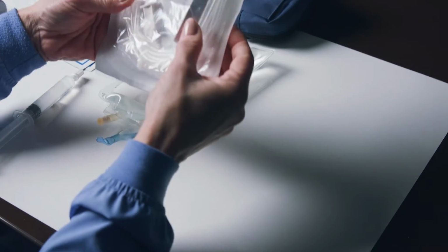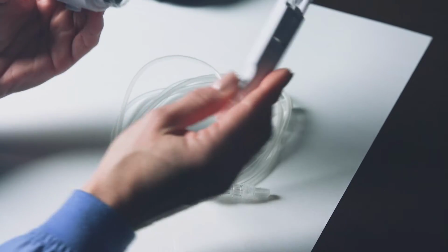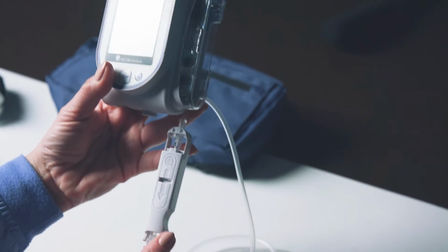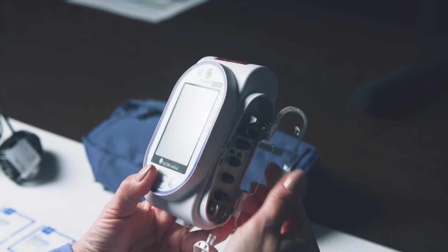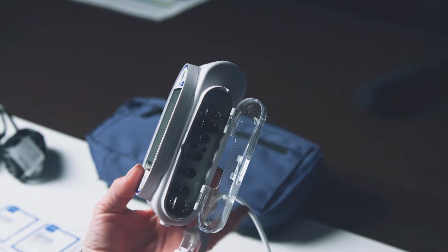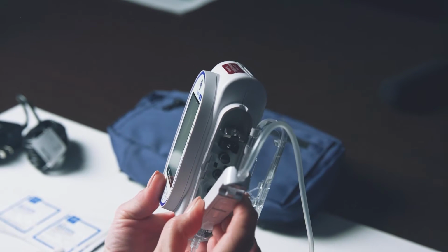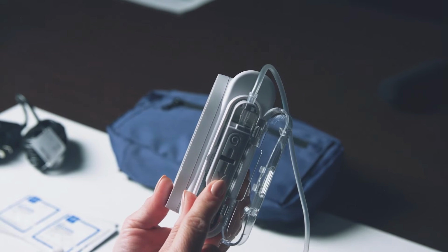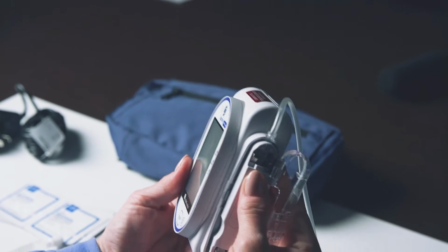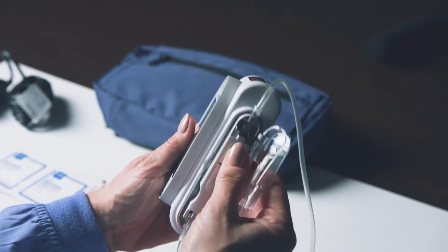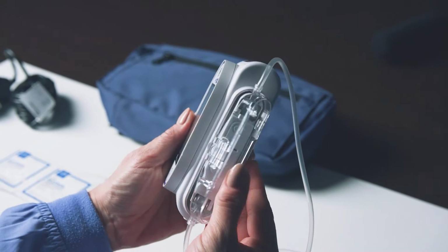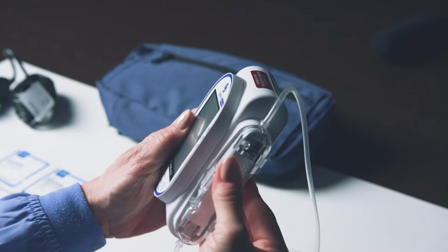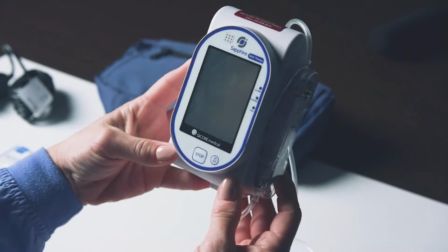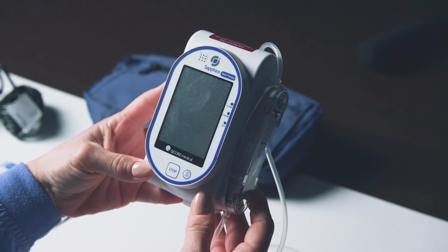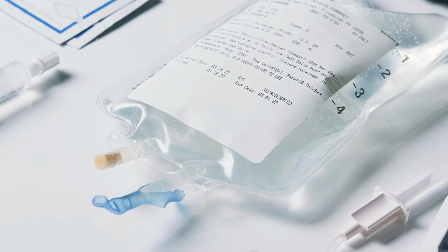Remove your Sapphire tubing from its packaging. Insert the IV tubing administration cassette at an angle by placing the saddle in first onto the round metal pegs at the bottom of the cassette's housing. Make sure the arrow on the cassette is pointing down towards the bottom of the pump where the on-off button is located. Press the cassette into the cassette housing by hinging it inward until it clicks in place, like this. Then close the safety door, ensuring it clicks closed.